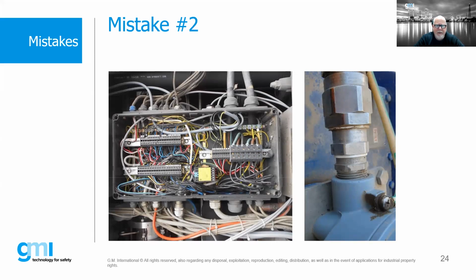The one on the left, there's actually a requirement for Ex e enclosures. Obviously, it's a mess, but there is a requirement, the maximum length of cable that you can run on the inside of an Ex e box. We can't do typical service loops running all over the place because we want to make sure that we minimize the amount of heat buildup, and cables on the inside of enclosures are resistive. They're going to generate some additional heat. So we have to be very careful in our installations with regards to Ex e.